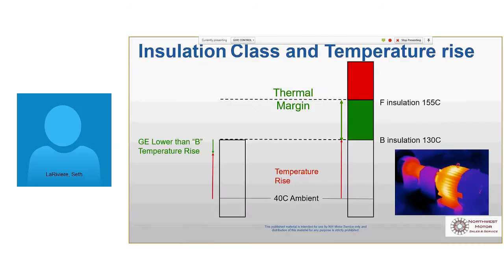Over time, if you have a motor that gets cycled frequently, maybe it starts and stops several times a minute, that motor's never going to live. It's just too much heat to dissipate if it doesn't run long enough to dissipate that heat, right? So motors that get slammed, start and stop all the time, elevators, those are always oversized a little bit just to deal with that heat. These motors, though, are designed to deal with that heat just in the way they're built.